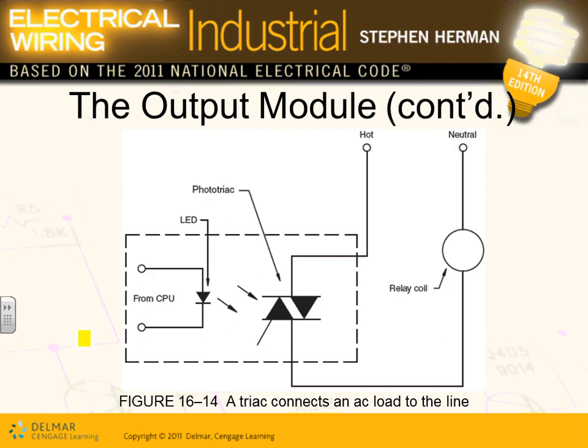So here's my CPU. I have 5 volt DC inside the processor. The processor puts 5 volt here. It's an LED. You put 5 volt across an LED, what does it do? It lights. Now when the light comes out of this LED, this is logic number 1. We're getting an output. This will be sensed by a photosensor, a relay photosensor. When it senses it, guys, it closes. Can you guys see that?